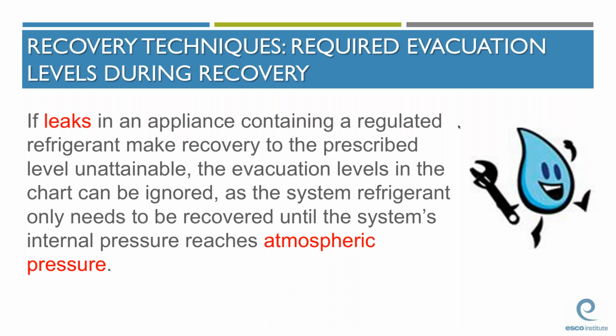All bets are off with regards to that chart we just looked at if the system's leaking. If the system is leaking and the prescribed vacuum levels can't be reached, the system refrigerant only needs to be recovered until the system's internal pressure reaches atmospheric pressure.